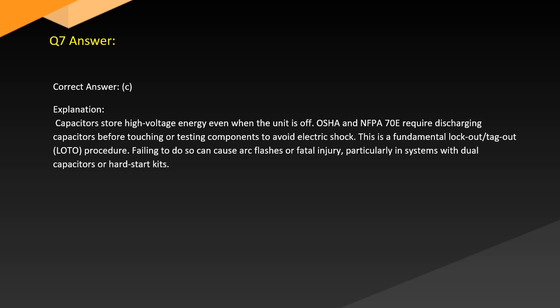Answer. Correct answer: C. Explanation. Capacitors store high voltage energy even when the unit is off. OSHA and NFPA 70E require discharging capacitors before touching or testing components to avoid electric shock. This is a fundamental lockout-tagout (LOTO) procedure. Failing to do so can cause arc flashes or fatal injury, particularly in systems with dual capacitors or hard start kits.